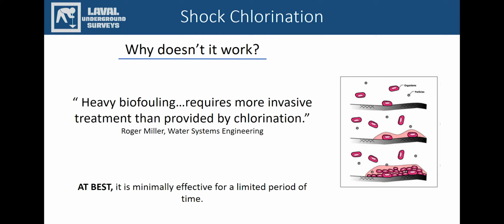1,000 parts per million of chlorine can be recommended, but these levels promote chloroforms. This much chlorine will likely agitate the biofilm as before, making it reproduce quicker. Strong chlorine solutions used for shock chlorination may damage biofilms but will not kill all the organisms in them, since the chlorine cannot fully penetrate inside or destroy all the slime filament-like structures.